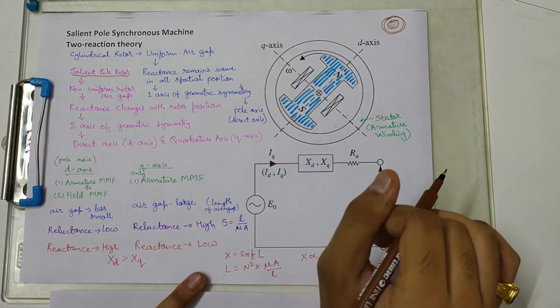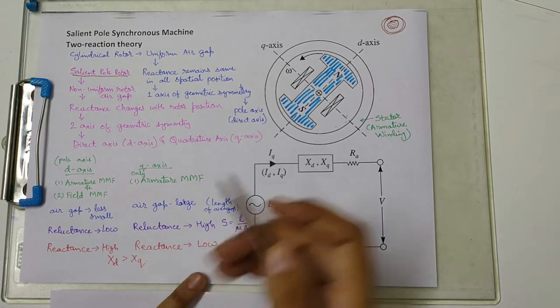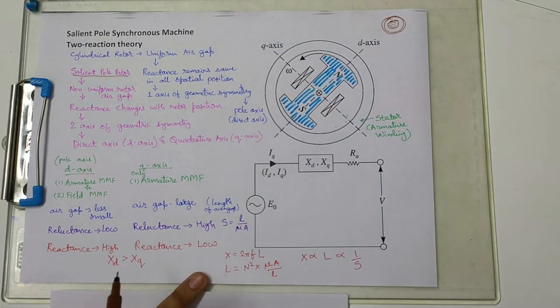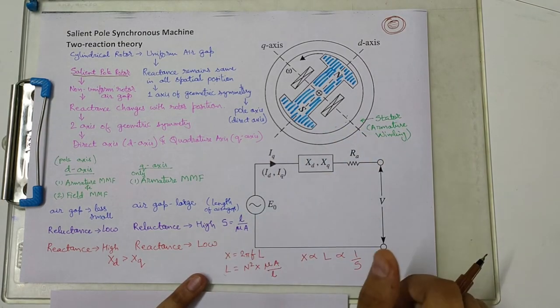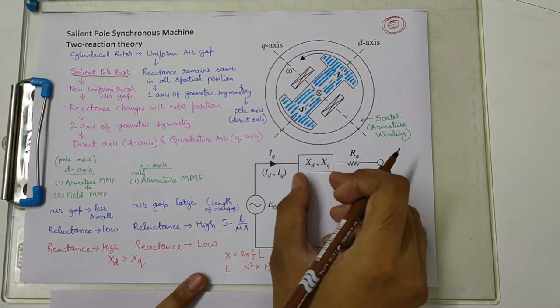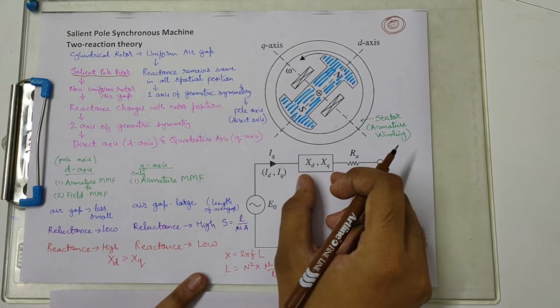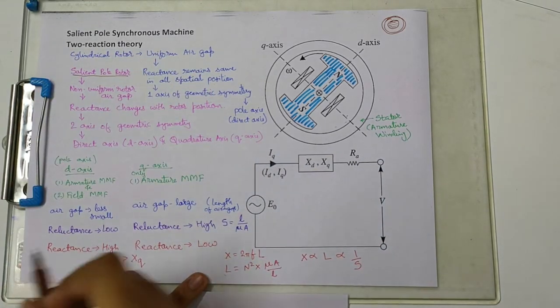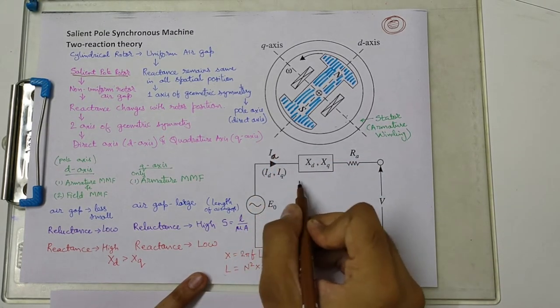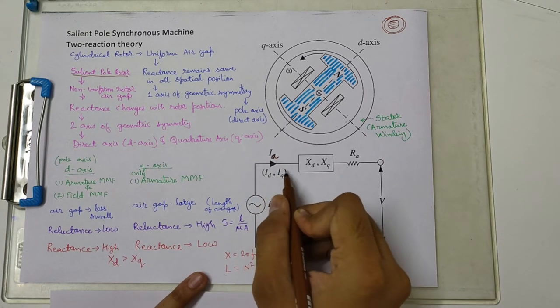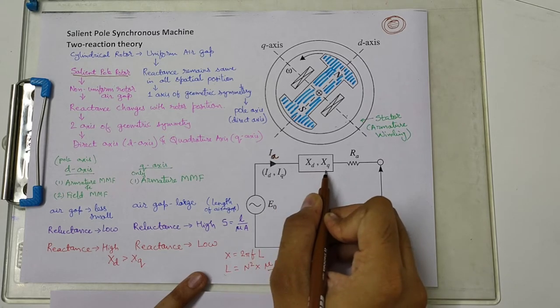This is the basis of two-reaction theory: we divide the reactance into two parts — direct axis reactance XD and quadrature axis reactance XQ — and the values of both are different. In the equivalent circuit, E0 is the no-load induced EMF in the armature winding and V is the terminal voltage. The synchronous reactance is divided into XD and XQ, and the armature current IA is assumed to have two components: a direct axis current ID and a quadrature axis current IQ, corresponding to XD and XQ respectively.